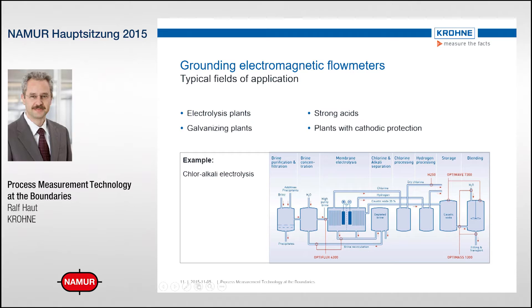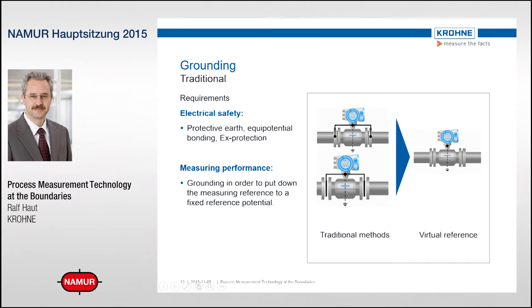These high currents cause disturbing currents and potentials on instruments due to non-proper grounding, leakage of instrumentation, or bad earthing. Electrical requirements include protective earth and equipotential bonding. In hazardous areas, electrical safety is critical. The measuring performance also requires electrical connections to establish a fixed reference potential, most easily achieved by grounding.